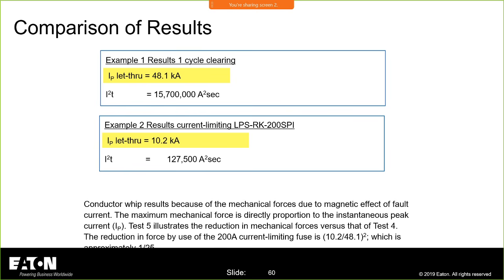My question, Johnny, would be, where would you use that fuse? Outside of a PV system, we do have 1,000 volt fuses for photovoltaic systems on the DC side. We've got 1,000 volt DC fuses. We've got 600 volt AC fuses, but the demand and the need for a 1,000 volt AC fuse, we're not seeing where that's used. If you know of applications where you need a 1,000 volt AC fuse, tell me where the application is. We're talking about that right now in the fuse standard to increase that to 1,000 volts. But as we're going through this journey, we're asking the question, where would you use it?